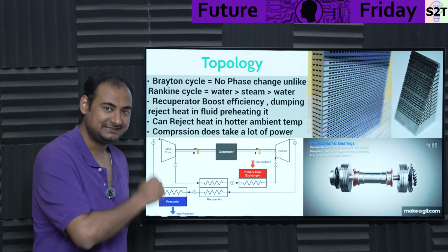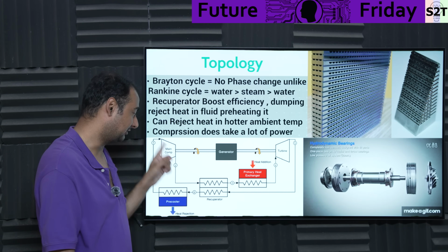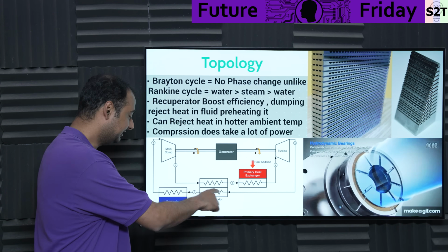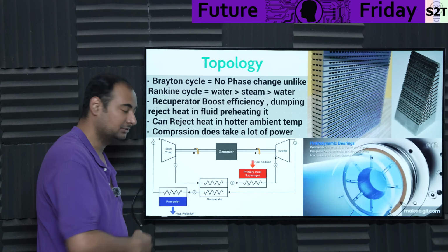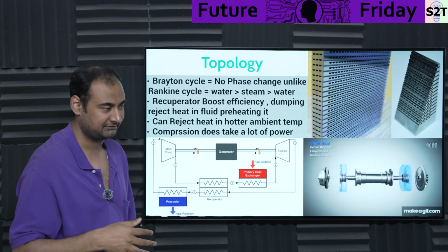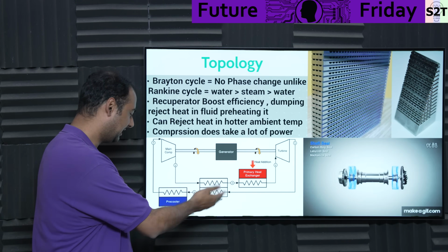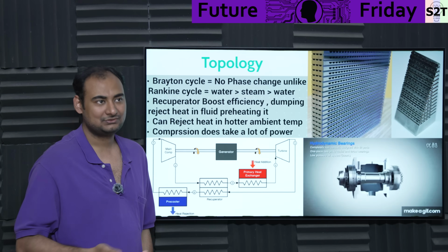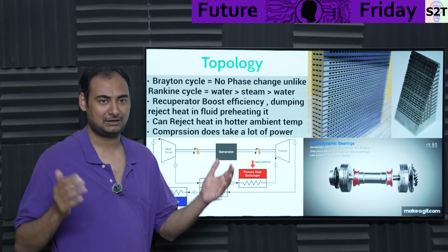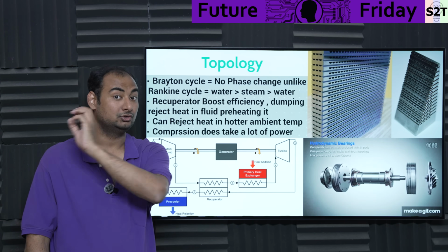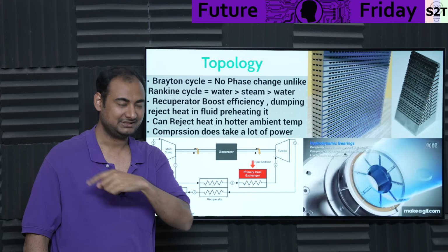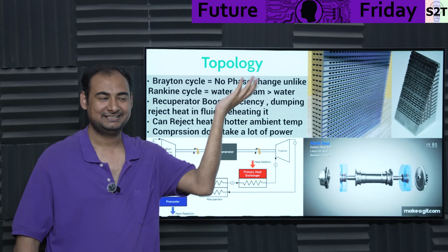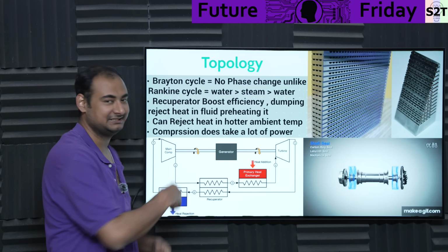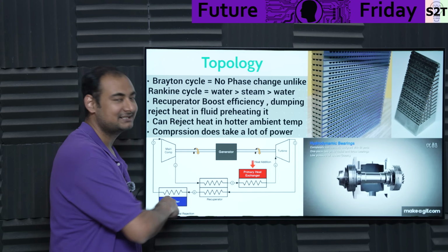The recuperator preheats the incoming stream from the compressor, and then dumps the remainder of the heat into the cooler, basically the radiator you have outside. Now you might ask, why not just close the system? If you close it, energy won't have a flow path. Energy must flow from the hot end to the cold end before you can extract it. If it doesn't flow that way, there's no flow at all, it will just heat up in pressure and go boom. So it must have a cold sink.